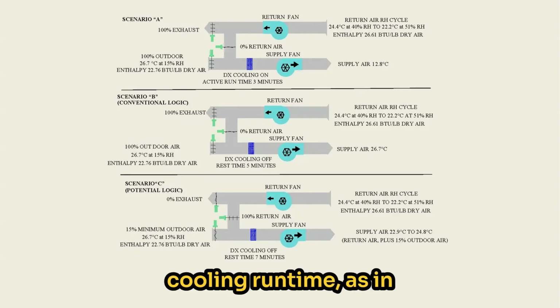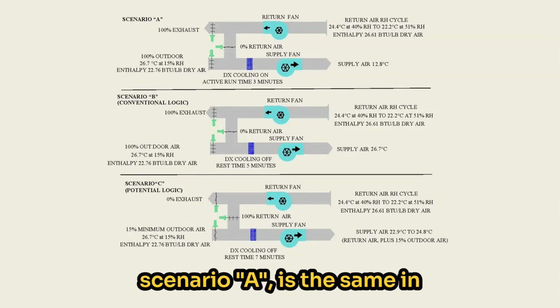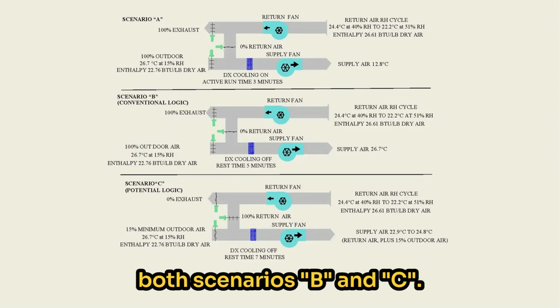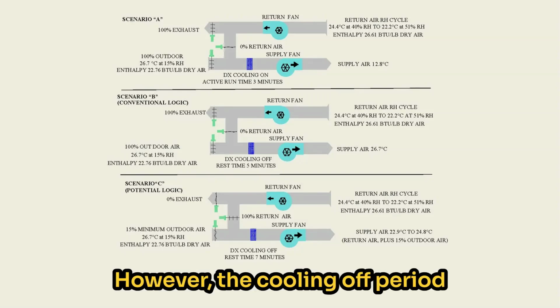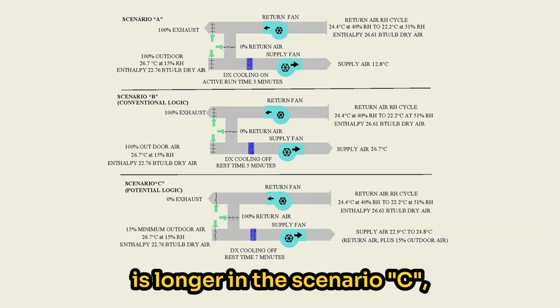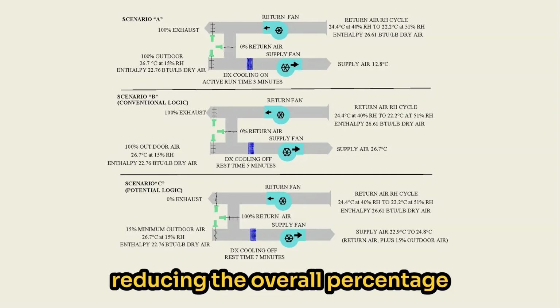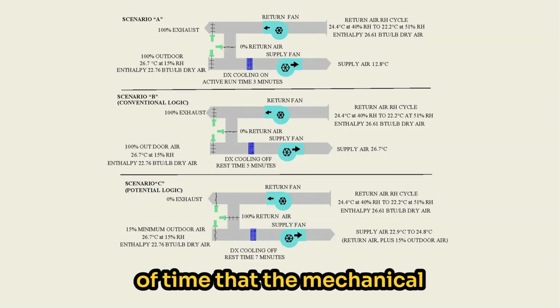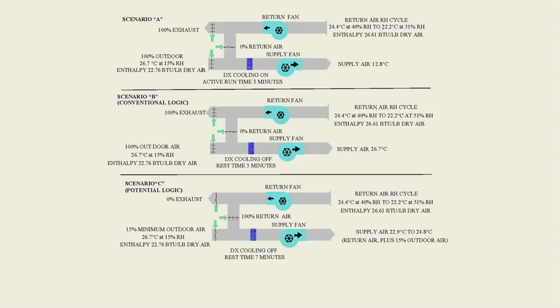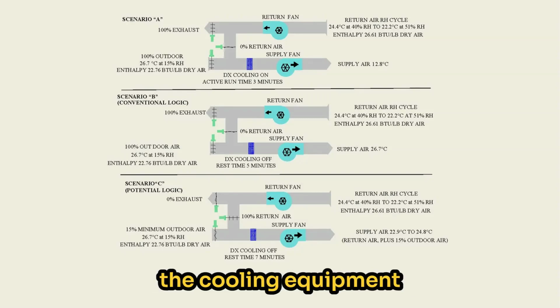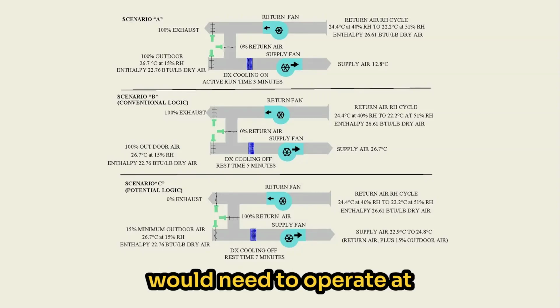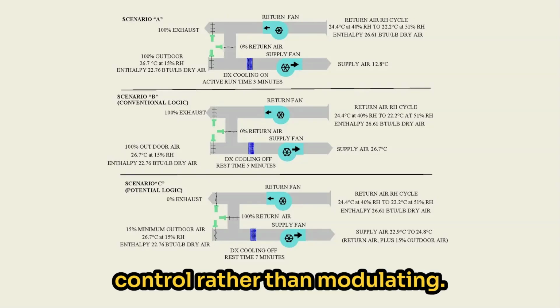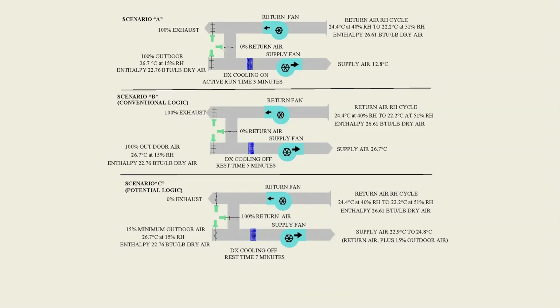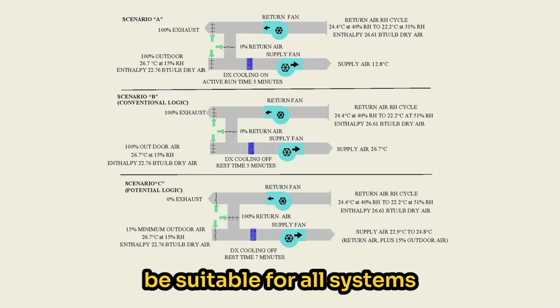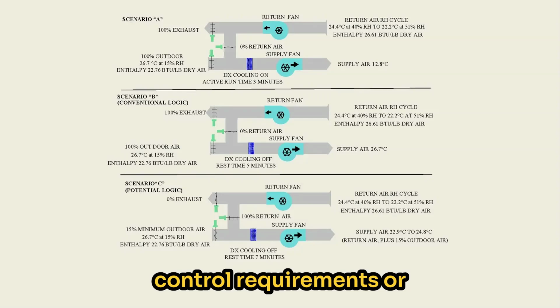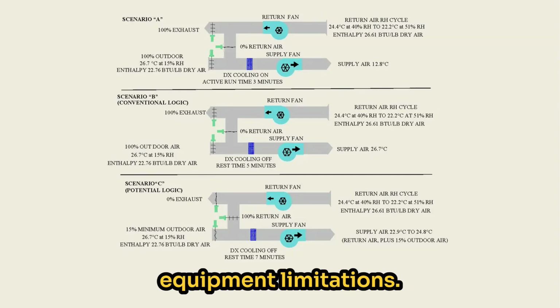The total mechanical cooling runtime, as in scenario A, is the same in both scenarios B and C. However, the cooling off period is longer in scenario C, reducing the overall percentage of time that the mechanical cooling must operate. To implement this strategy, the cooling equipment would need to operate at 100% on-off control rather than modulating. This requirement may not be suitable for all systems due to space temperature control requirements or equipment limitations.